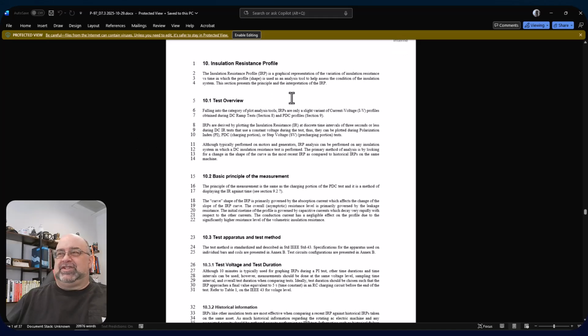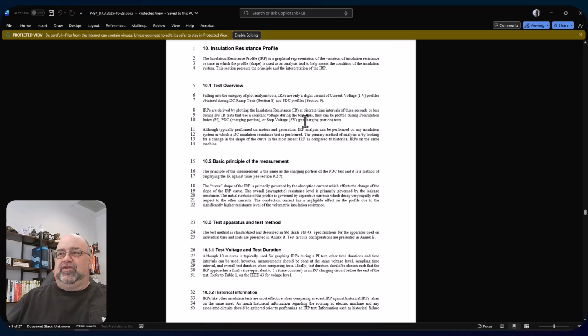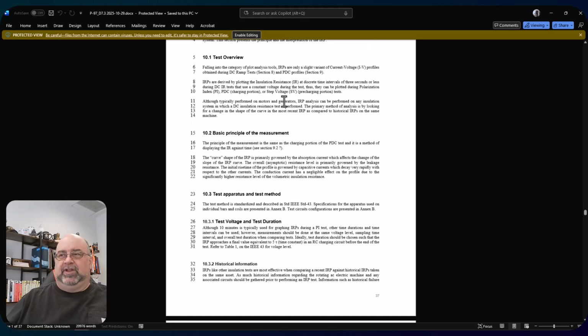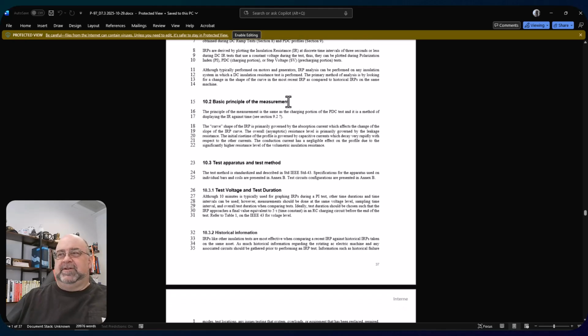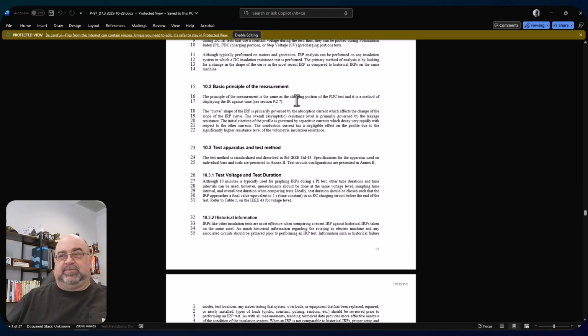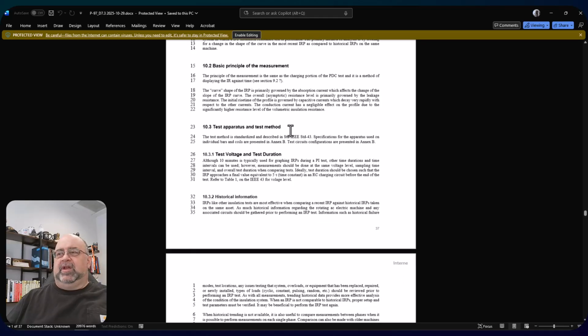So, insulation resistance profile, the overview. It's very similar to the PDC one that I just breezed through and didn't talk about, which is about charging and discharging and how the curves look and how long it takes to discharge. It gives different indicators. However, most people have access to this type of test, whether through a PDMA or an amp probe, high voltage tester, that kind of thing, in order to get the curve.